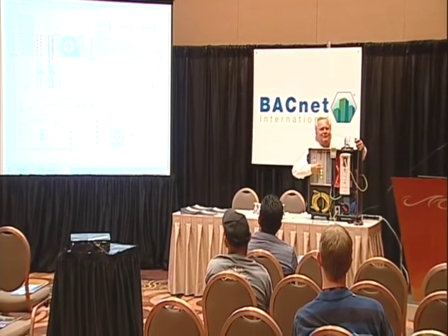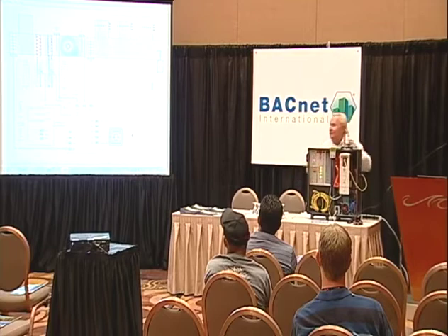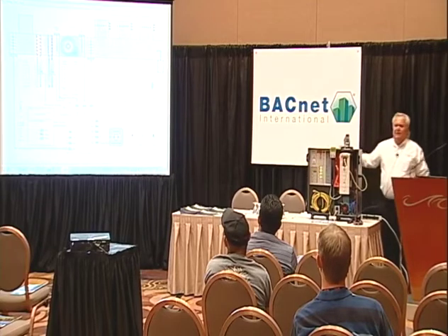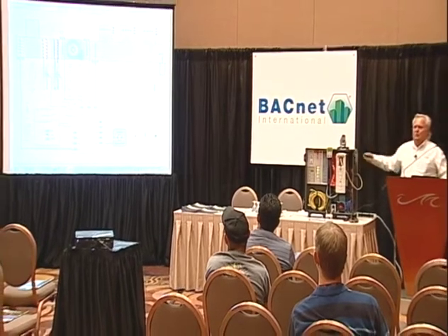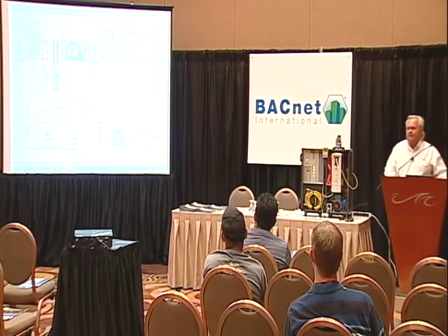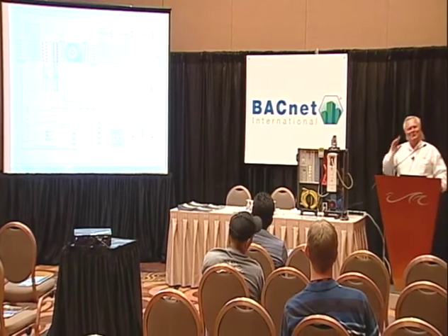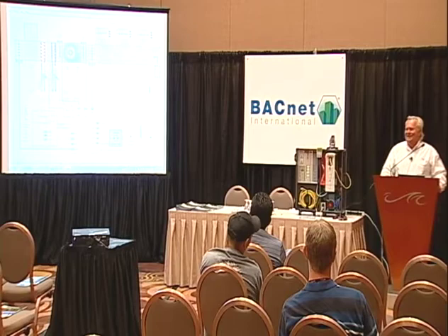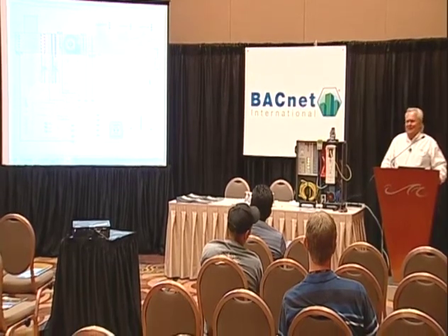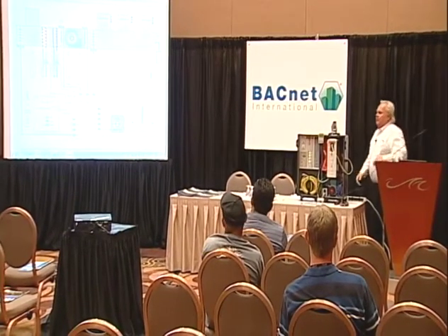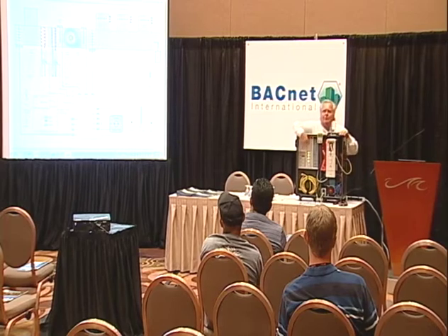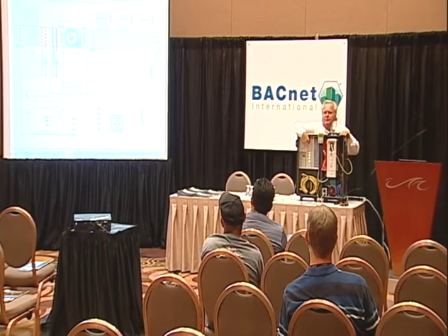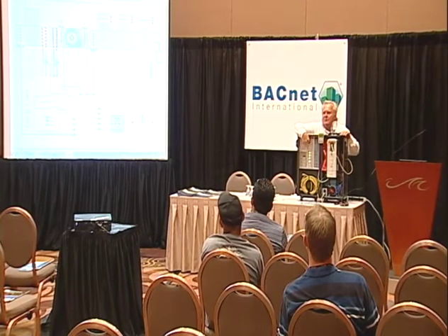So if I can find digital input 2 here, close it. Now we start ramping that fan up and supplying pressure. Now this motor's got a bad bearing in it. I keep it that way so that you can hear something going on out in the audience. So I purposely did not replace this motor. And you'll see from the graphic, as pressure goes up, the drive slows down. As pressure goes down, the drive speeds up.